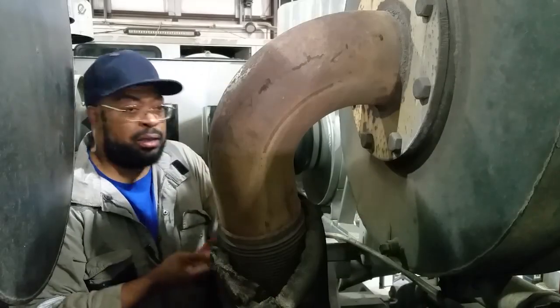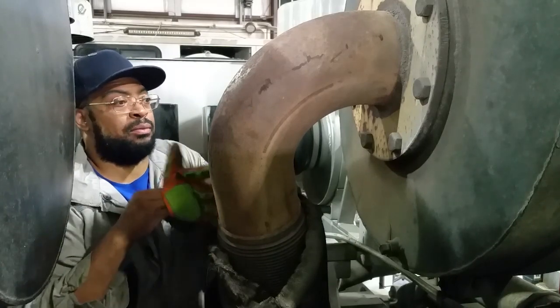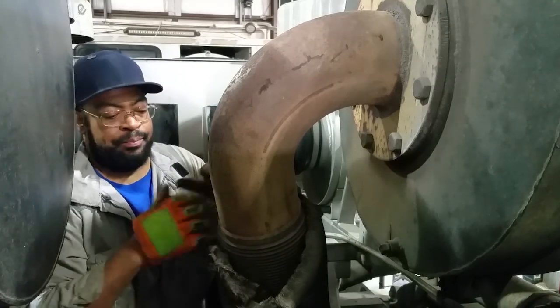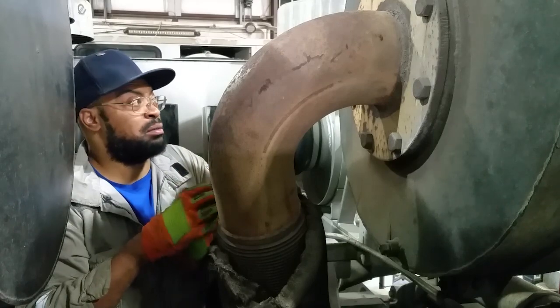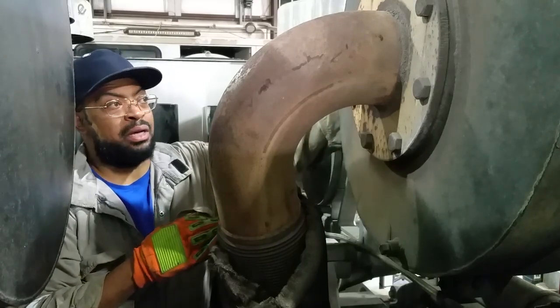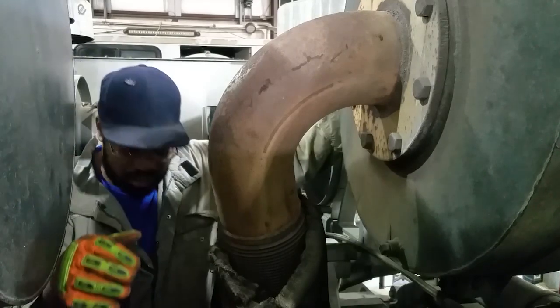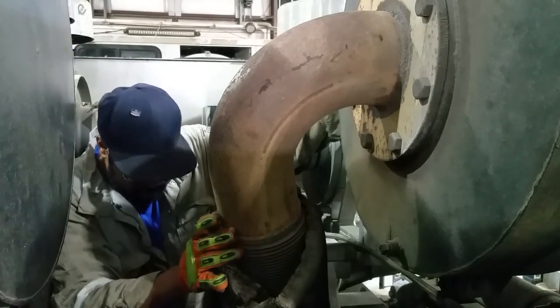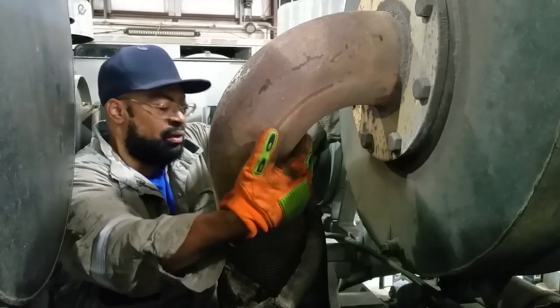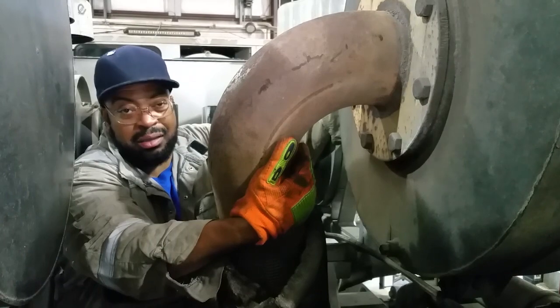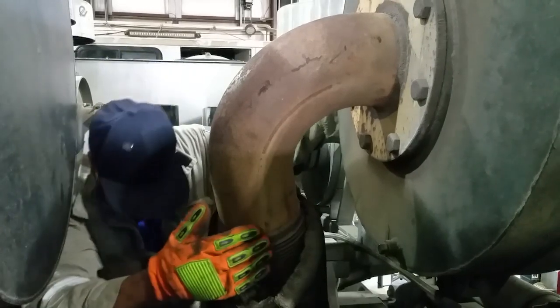And what I'm looking for is leaks and stuff. I'm going to end up putting this pump on the test stand, running some fluid through it, pressuring it up, probably about 3,000 to 4,000, for 10 to 15 minutes, and call it a wrap. Make sure everything pumps and runs good, and there's no leaks. I may leave it on there for an extended period of time, but I think it's getting close to lunch.